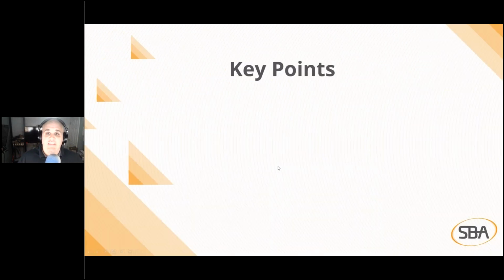All right. That being said, at the end of each of these sessions, I'm going to have some key points. And these are kind of what I want you to take away. The first is IAQ is only as good as your measurements. I firmly believe we're moving into a retrofit market. The capital construction market seems to be collapsing around us, and it's kind of difficult to make an argument to build a bunch of new buildings when you're having trouble occupying the ones you already have. So with that being said, I feel like we're going to enter an actual retrofit market. And with this retrofit market, it's going to be driven by actually having data. Now, IAQ, when we want to drive it, whether it's ASHRAE 62 or ASHRAE 55, which is thermal comfort, and we're driving temperature, humidity, CO2, et cetera, it's only as good as your data measurements. So just because you have humidity sensors or CO2 sensors does not mean that those elements are still valid.